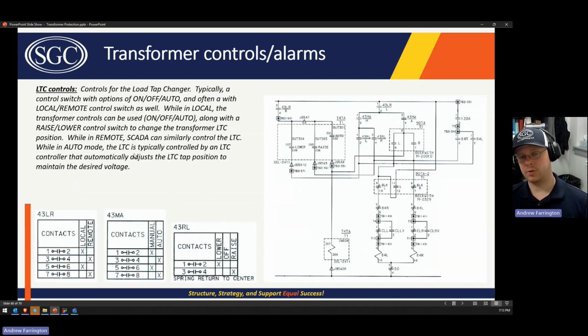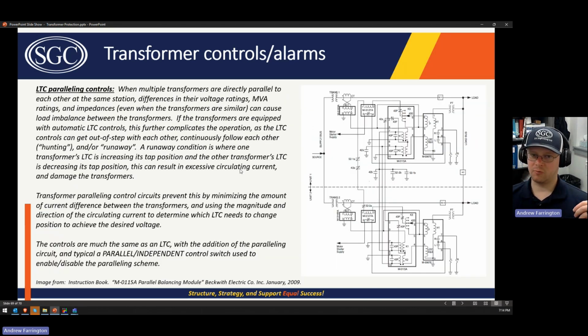There's also LTC controls. We talked about this quite a bit last class. This is an example of an LTC control circuit where you've got a local and remote control. The remote control has the ability to raise, lower, or put the LTC controls in auto. Or these are control switches in the transformer mechanism housing, so you can put it in manual and then manually raise or lower the transformer LTC position, or you can put it in auto and then the LTC controller automatically raises and lowers it. So this is just an example of the different control switches and a sample schematic that you might have for your transformer LTC controls. There's also transformer paralleling controls.